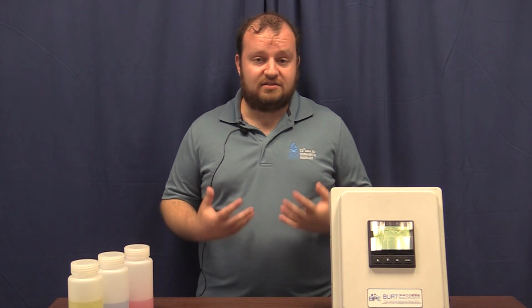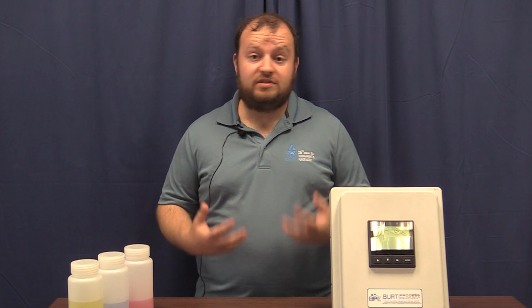So the possible cause is that you have a chip in the glass on the electrode itself, causing low impedance. The way to fix this is to properly inspect the probe to see if there's any chipped glass, and if need be, you can replace the probe, and then once you wait 30 seconds, you can perform an impedance test, and this will clear the alarm.